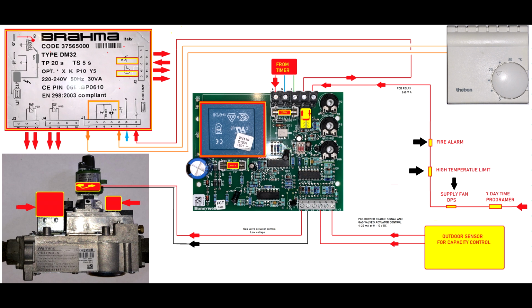But then when you enable the timer, instantly you will have 3 alarms that will be checked because they're in line with that signal. So you'll have a fire alarm, you'll have a high temperature alarm, you'll have a differential pressure switch of the supply fan. You can have many safety alarms. If you're a control engineer, obviously if you use logic gates, you'll use an AND feature. And if you are an electrician, obviously you will say that this is a series connection.